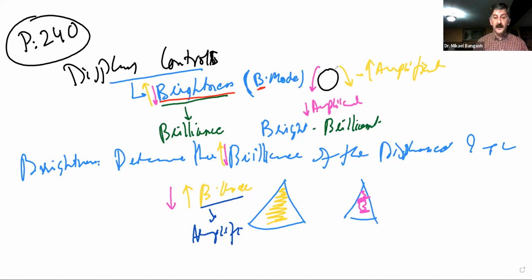So if we increase our amplification, which is achieved by turning the B mode knob clockwise, we will increase the brightness of the image, or we increase the brilliance of the image that is displayed. Whereas if we turn counterclockwise on our B mode knob, that reduces the amplification of the signal. Our image is going to be overall reduced in brightness or brilliance. So brightness just determines the brilliance of the displayed image.